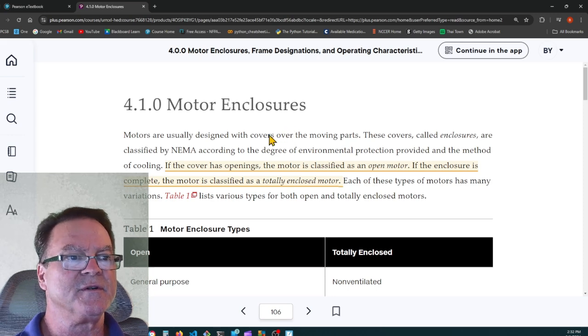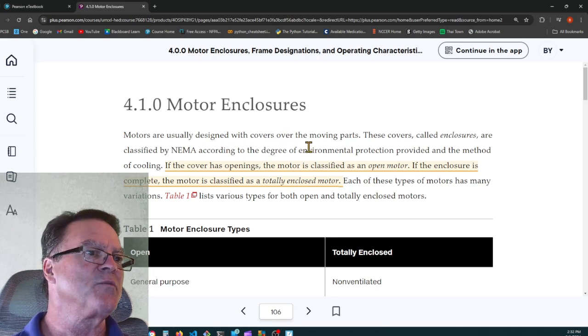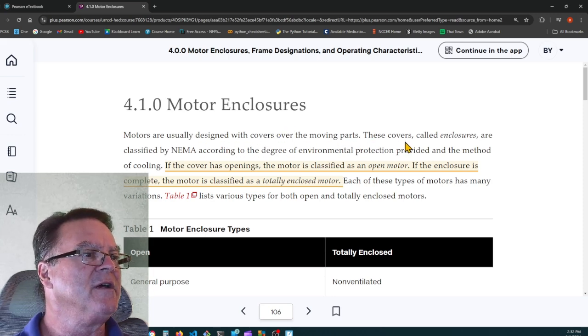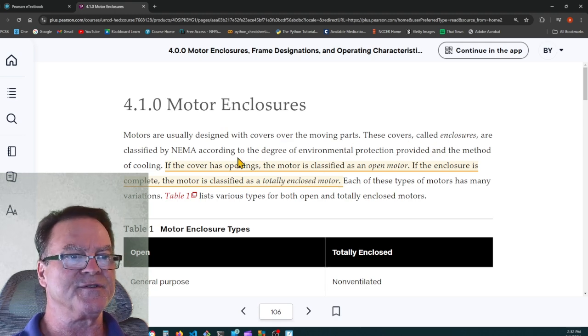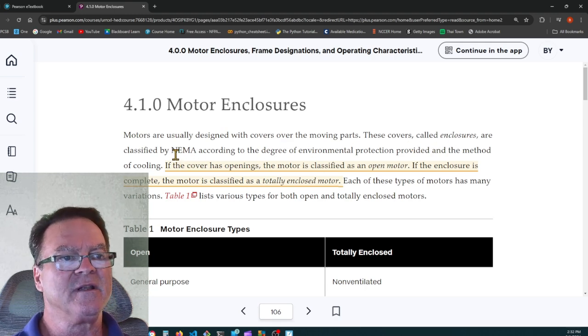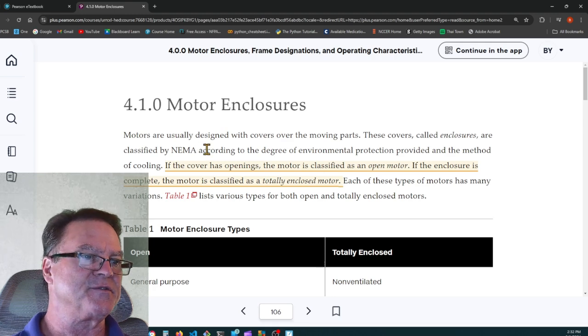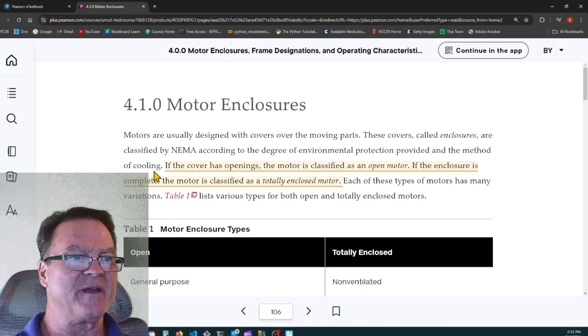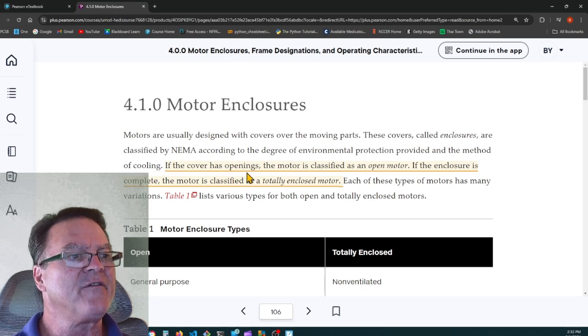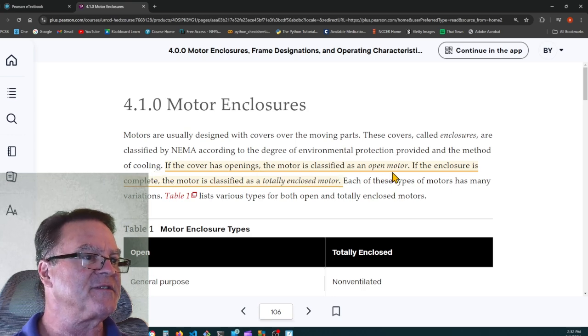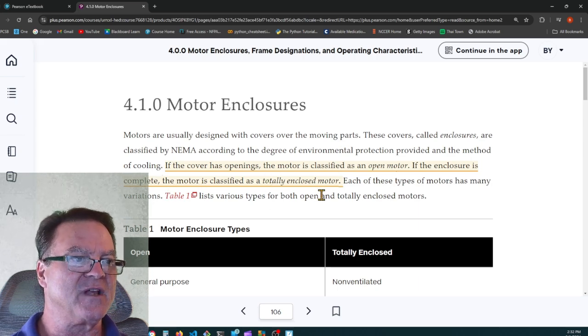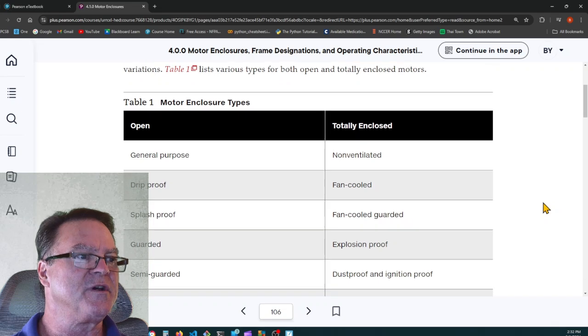4.1.0 Motor enclosures. It says motors are usually designed with covers over the moving parts. These covers, called enclosures, are classified by NEMA, the National Electrical Manufacturers Association, according to the degree of environmental protection provided and the method of cooling. It says if the cover has openings, the motor is classified as an open motor. If the enclosure is complete, the motor is classified as totally enclosed.